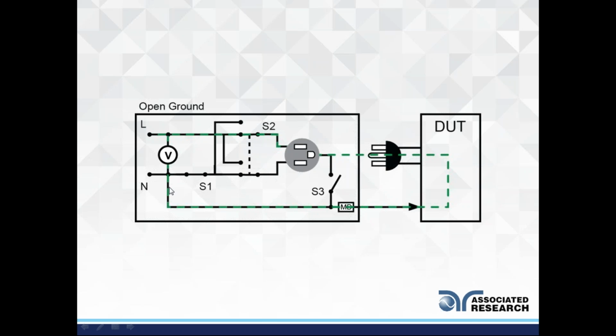All right, so I hope that gives us a clear background of what these fault conditions are, what they do, and now that I'm putting myself in the position, I probably still would run the test with ground closed because the more data we get, the better we understand how our products behave.